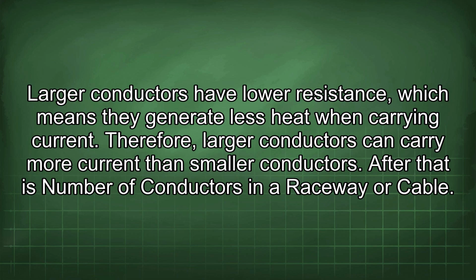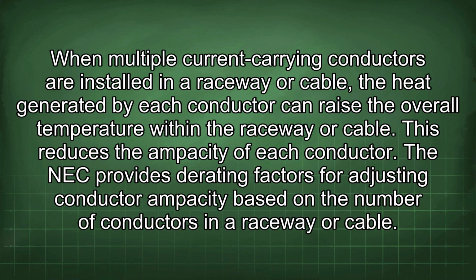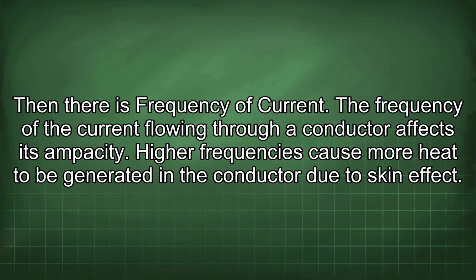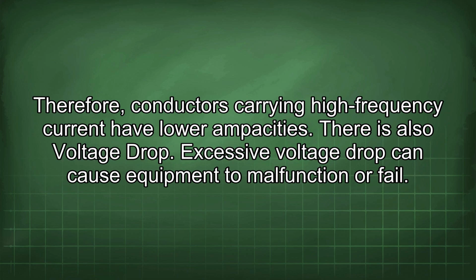After that is the number of conductors in a raceway or cable. When multiple current-carrying conductors are installed in a raceway or cable, the heat generated by each conductor can raise the overall temperature within the raceway or cable. This reduces the ampacity of each conductor. The NEC provides derating factors for adjusting conductor ampacity based on the number of conductors in a raceway or cable. Then there is frequency of current. The frequency of the current flowing through a conductor affects its ampacity. Higher frequencies cause more heat to be generated in the conductor due to skin effect. Therefore, conductors carrying high frequency current have lower ampacities.